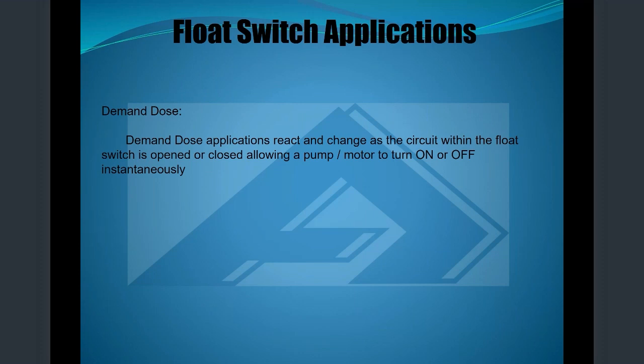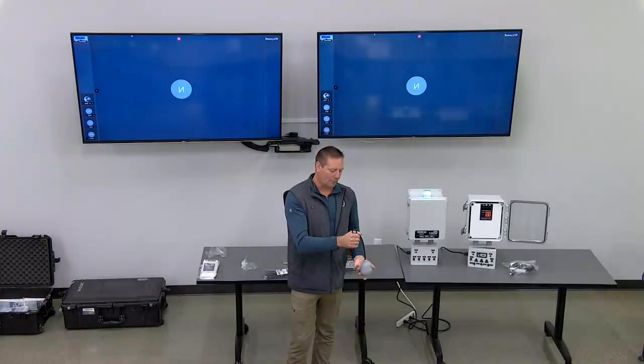Okay, demand dose means that in a normal sewage application, we'll say we use a wide angle control or pump float, and when the float comes up, the circuit closes, your pump comes on demand. So right now it's saying pump turn on. When it comes down, pump turns off. So on, off activation. On a time dose system, you'll have a timer enable float.